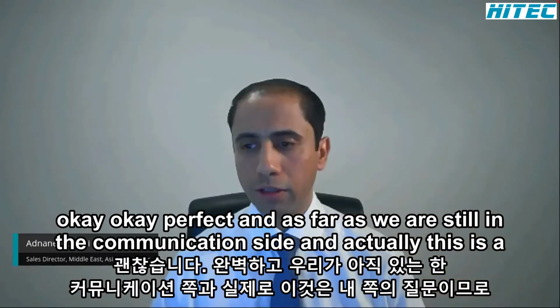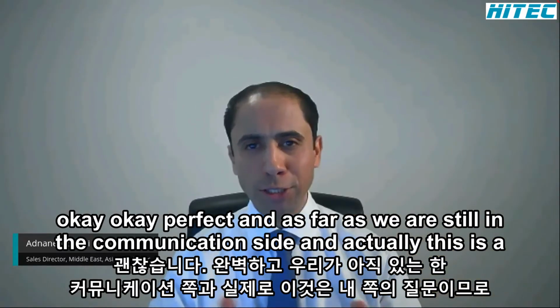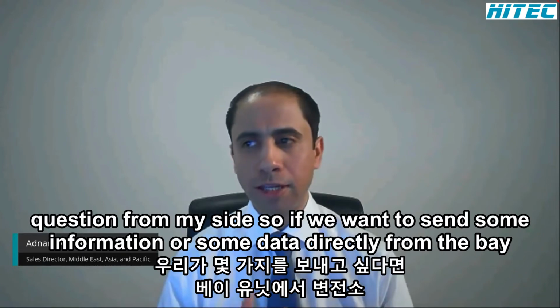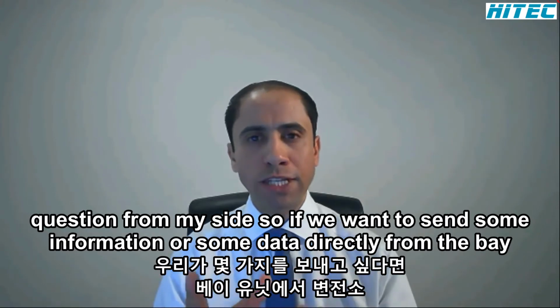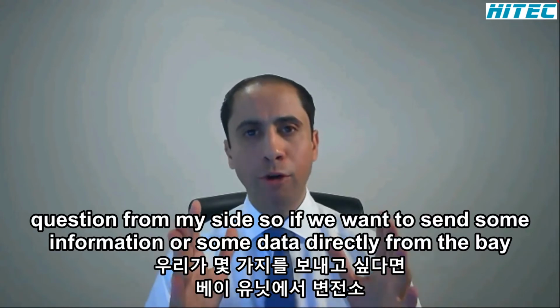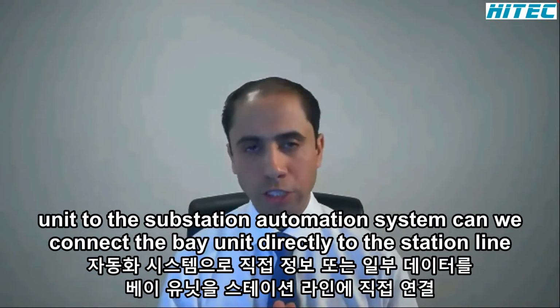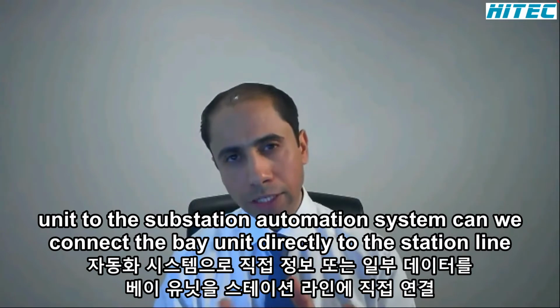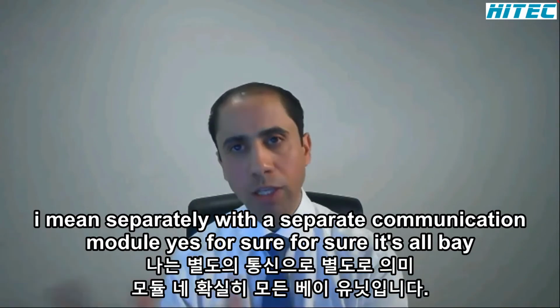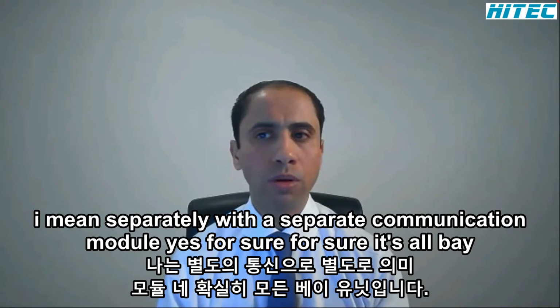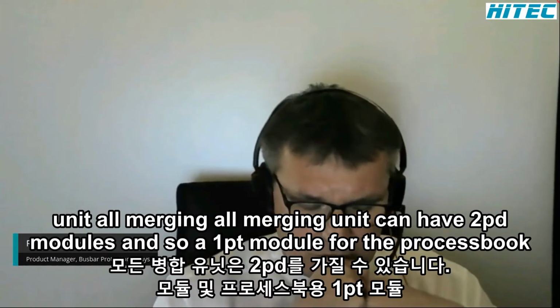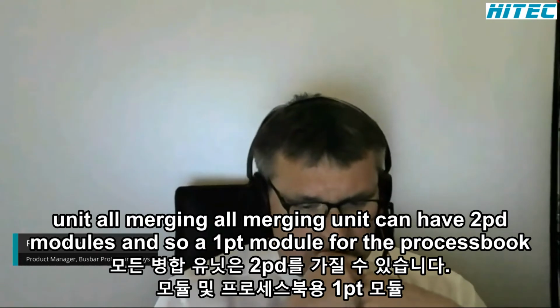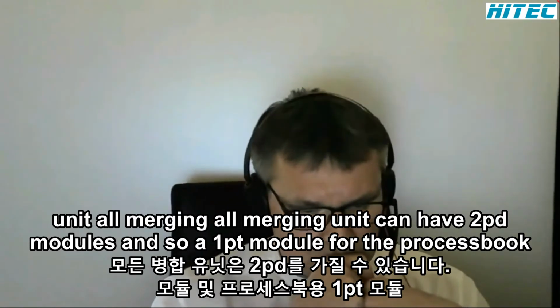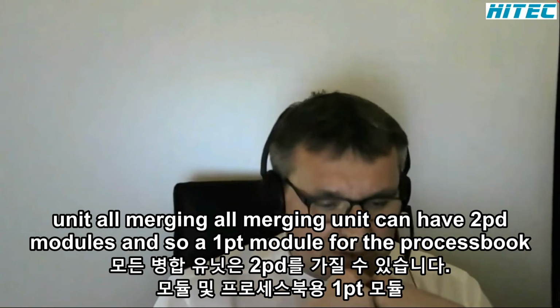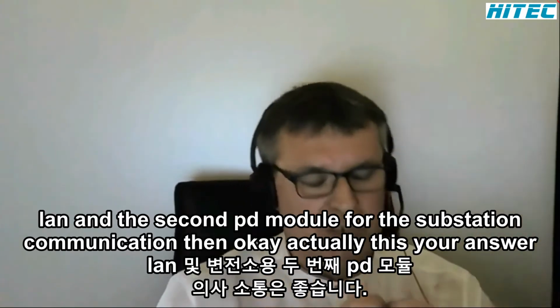Okay, perfect. And as far as we are still in the communication side, and actually this is a question from my side. So if we want to send some information or some data directly from the bay unit to the substation automation system, can we connect the bay unit directly to the station LAN? I mean, separately with a separate communication module? Yes, for sure. All bay units, all merging units can have two PT modules, and so one PT module for the process bus LAN and a second PT module for the substation communication LAN.